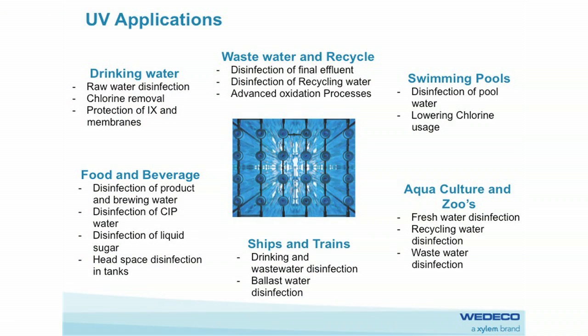We have very good stability in terms of fluctuating water temperatures, and a very long lamp life, about 12,000 hours. The UV applications, this is also growing as people are becoming more aware of the abilities of UV. Pretty much targeting the same range of uses as ozone, where you're not looking for a secondary disinfectant or a secondary chemical in your process. A growing use is in your ultra pure water supplies, into like the pharmaceutical industry, where you don't want to change the chemistry of the water, so this is where UV then becomes effective.